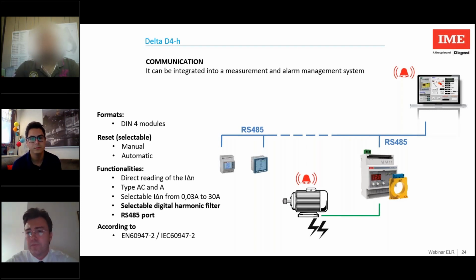Okay. From Boris, do you have a filter function to select only 50 Hertz, for no influence from, sorry. As I said, it is not type F, it is the F series, the Delta D4H and the F series. The F series takes only the nominal frequency, the 50 Hertz, or whatever frequency it works at; if it's working at 60 Hertz, it takes only the 60 Hertz.